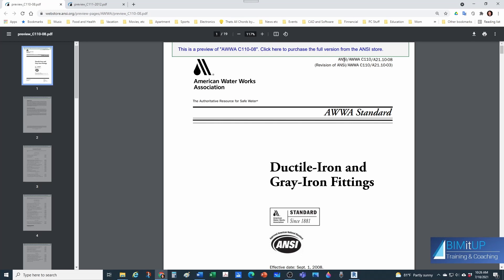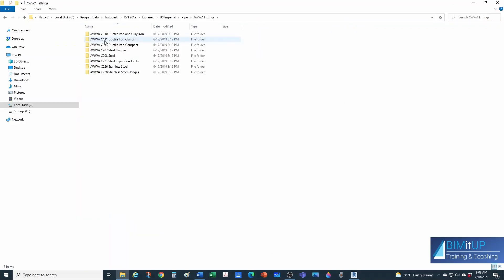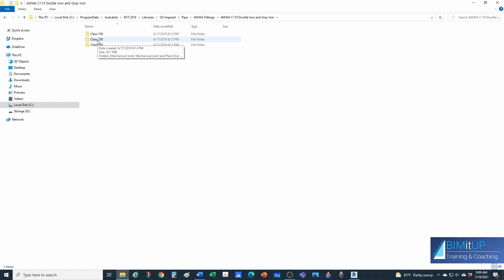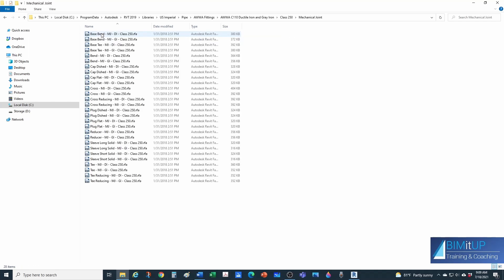AWWA is the American Water Works Association — it's simply a standard that manufacturers want to comply with. This is the American National Standards Institute, so you can go online if you want to read more about that. What matters to us here is that our fittings are going to be manufactured under the C110 standard. We're going to go under C110 Ductile Iron and Gray Iron, Class 250, and then under Mechanical Joint.